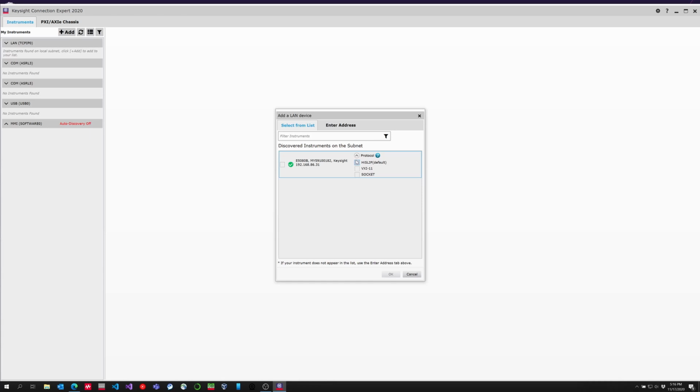So I always recommend my customers, if HiSLIP is available, use HiSLIP. If VXI-11 and sockets are available and there's nothing tying you to legacy, use sockets. Otherwise, use VXI-11 like you've always used.